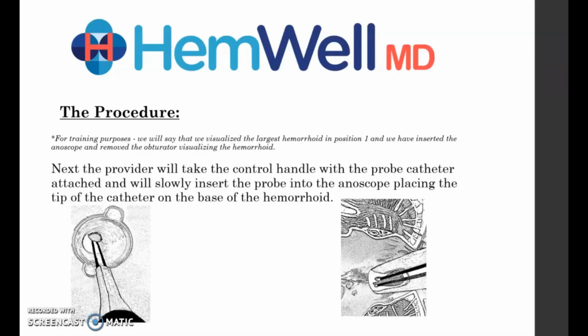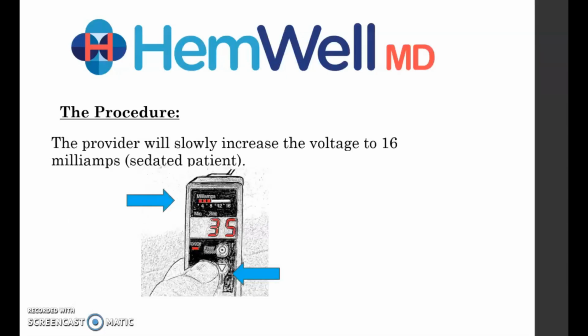The provider will take the control handle with the probe catheter attached and will slowly insert the probe into the anoscope, gently placing the tip of the catheter at the base of the hemorrhoid. The provider will slowly increase the voltage to 16 milliamps if the patient is sedated. If they are conscious, the provider will likely keep the voltage around 6 to 8 milliamps, and treatment time is around 5 minutes. It is important to note that the circuit is only complete when the probe tip is touching the patient. The control handle will not register any voltage being delivered if the probe tip is not touching the patient.